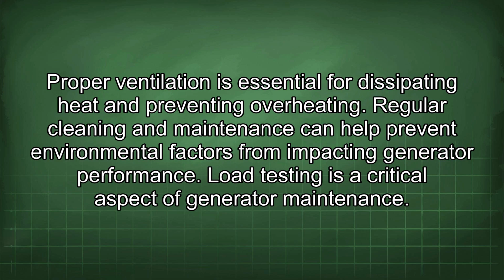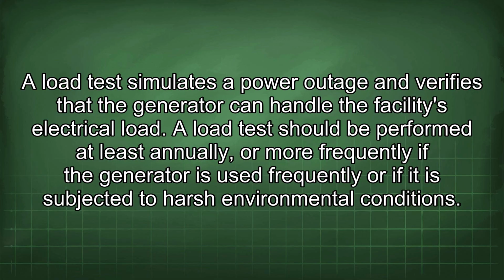Load testing is a critical aspect of generator maintenance. A load test simulates a power outage and verifies that the generator can handle the facility's electrical load. A load test should be performed at least annually, or more frequently if the generator is used frequently or if it is subjected to harsh environmental conditions.